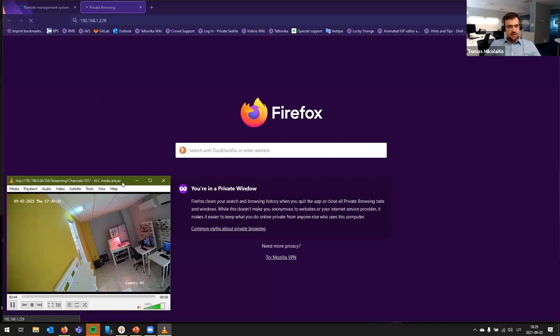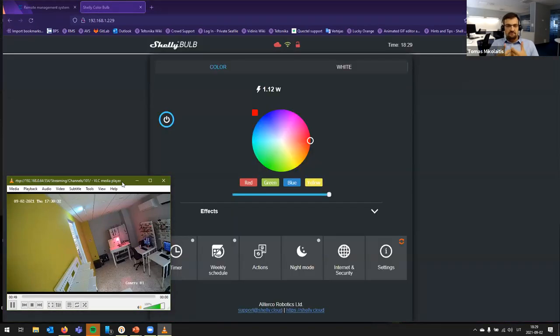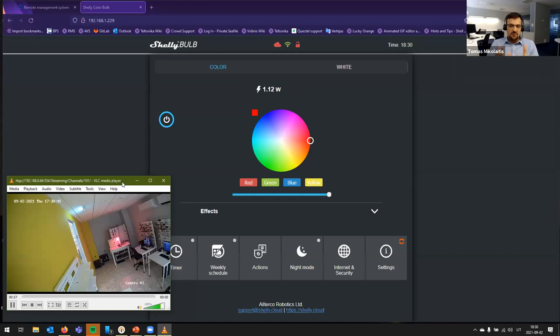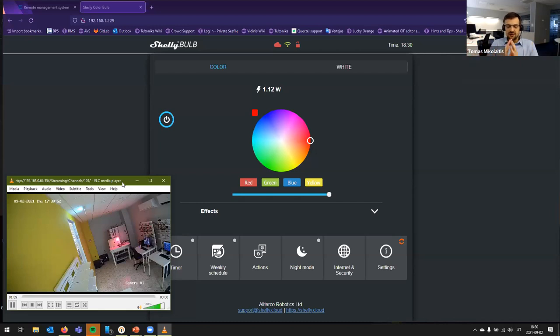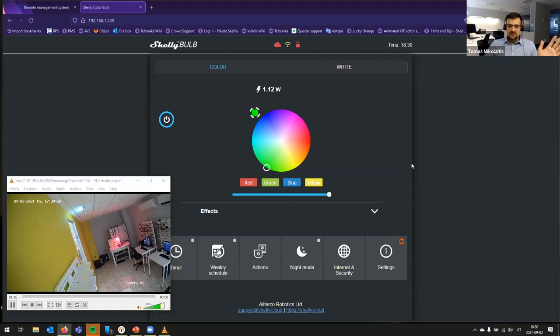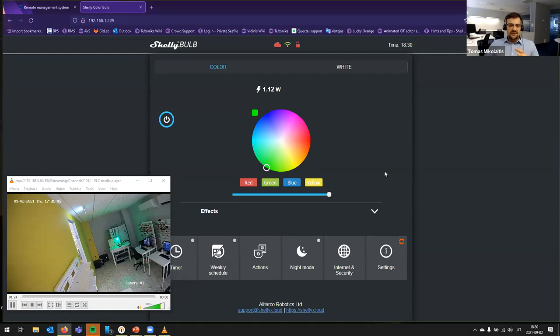And just imagine that it might be the process, and we have to check it remotely. What is happening with this? Maybe it's everything okay, but some error is left in the PLC itself. So, for this, let's connect to our device and see what is happening there. And while it's loading, this communication, I see that when entering this kind of device, we can have logs, we can have controls of it, and if you imagine the PLC you can have a number of parameters here. Okay, here I see that you can see that in logs, the issue was removed hours ago, and this is just a redundant message that shows that everything is okay.